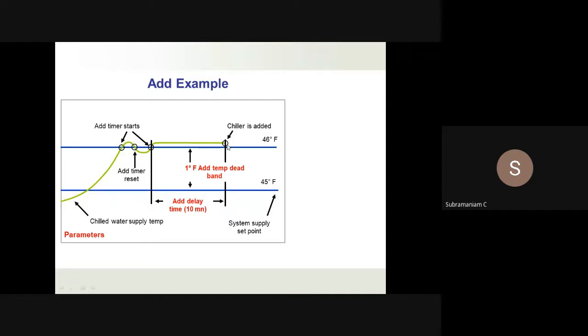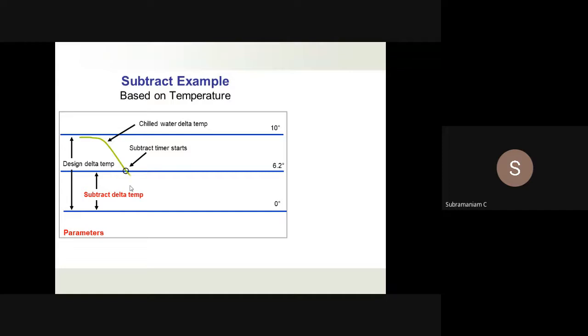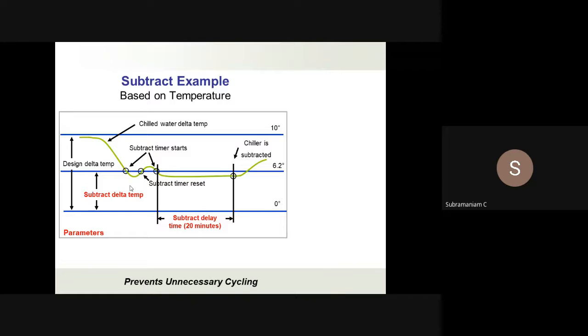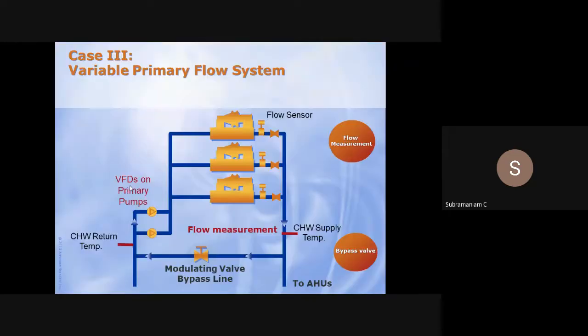Once you add one more chiller and primary pump, then the temperature comes down. So this operation will keep on continuing for every chiller. So this is the addition of chillers. And for subtraction of chillers, you do it based on the delta T between the supply and the return water temperature. This is one of the good methods of doing addition and subtraction of chillers, and that will take care of energy saving on the chiller plant.